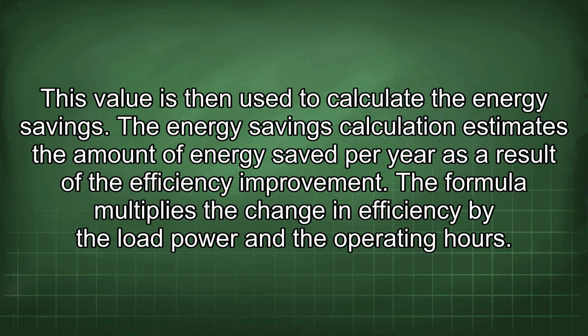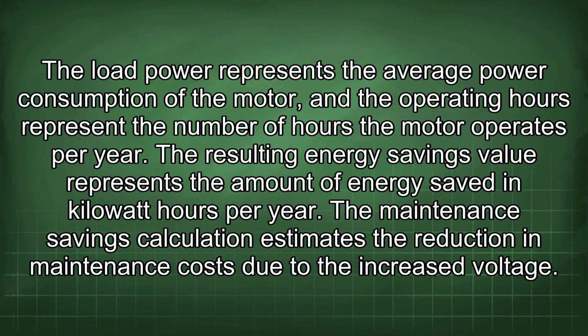The energy savings calculation estimates the amount of energy saved per year as a result of the efficiency improvement. The formula multiplies the change in efficiency by the load power and the operating hours. The load power represents the average power consumption of the motor, and the operating hours represent the number of hours the motor operates per year. The resulting energy savings value represents the amount of energy saved in kilowatt-hours per year.